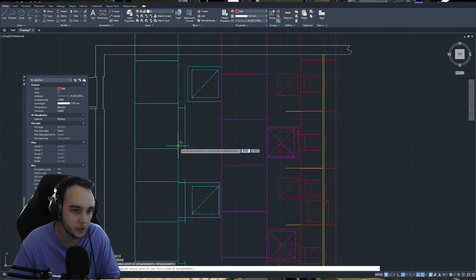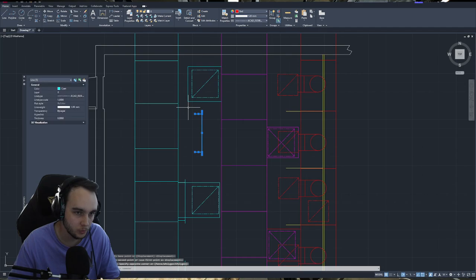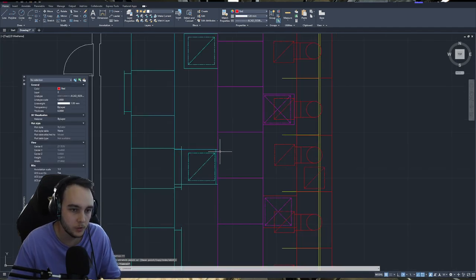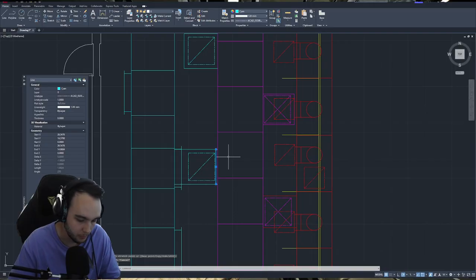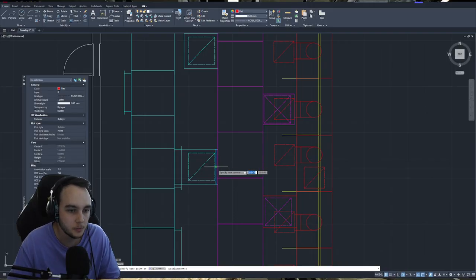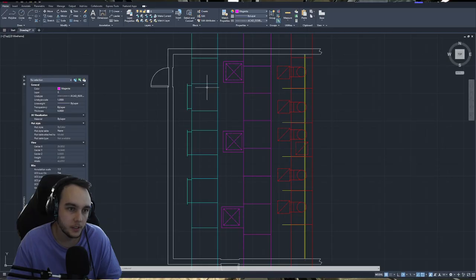Because if you put them too close to the supply, it's just going to short cycle, and then your room's not really going to do anything. So I'd actually probably do something like this. I'm going to really quickly change this around, and then we'll jump back to it once it's all done. Alright, so basically all I've done is switched the return grills from one side to the other, kept all of what looked like diffusers on the side that they were, and just connected them to what looked like the supply air duct instead. It keeps it away from the exhaust air, so you don't have to worry about the supply getting sucked into the exhaust, or short cycling with the return, pardon me.